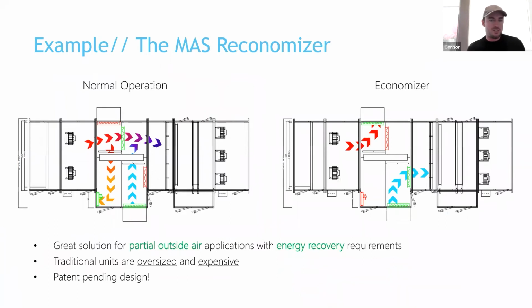This is an example called the MAS Reconomizer. This is a solution that we could use for partial outside air applications where you still need energy recovery. Traditionally, units in this criteria are oversized and expensive. Half the unit is dedicated to energy recovery, and the other half is dedicated to a supply air tunnel. So what we've done at MAS is we've combined the economizing and the energy recovery section into this center section.